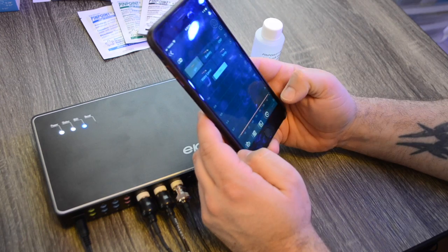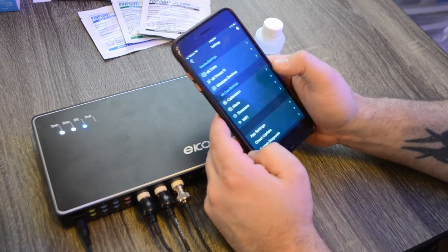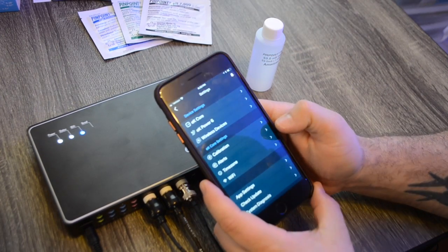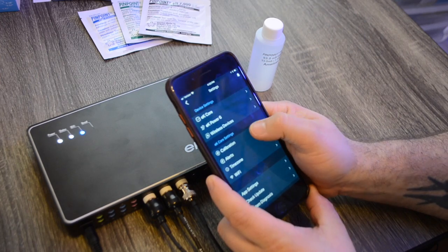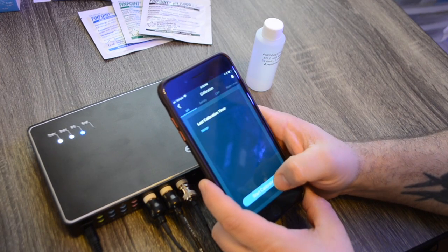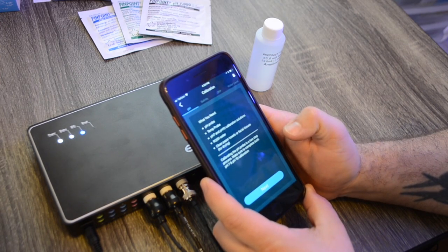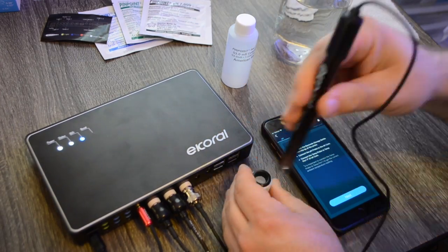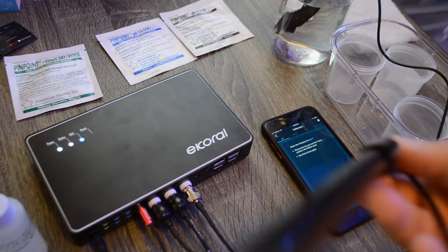making sure that you are calibrating your probes, because it's important to calibrate your probes every 6 months. Some people do it even more frequently than that. Ultimately, it is important to calibrate your probes as often as you possibly can, due to the fact that you are relying on that information that that probe is providing you.